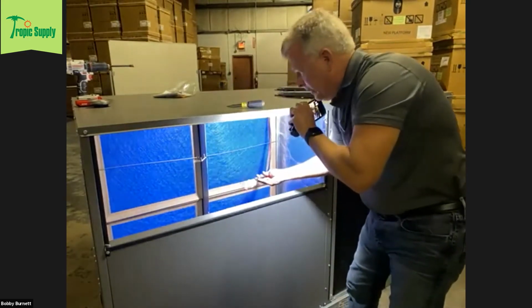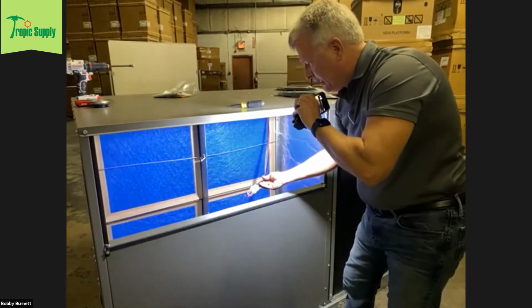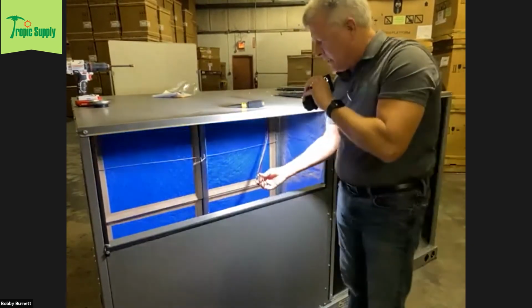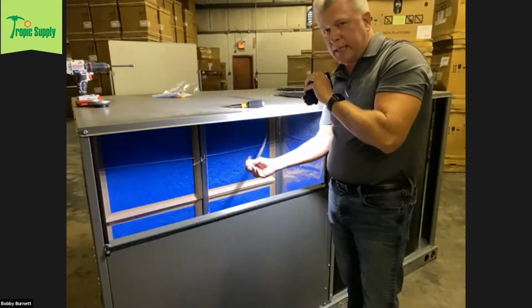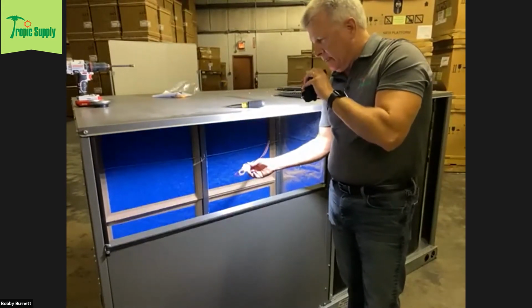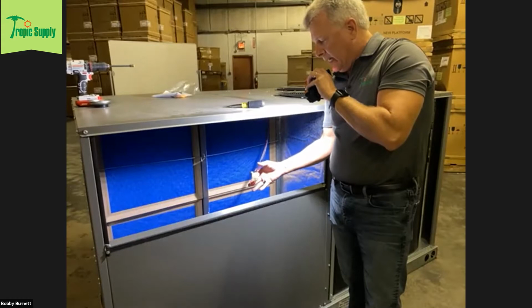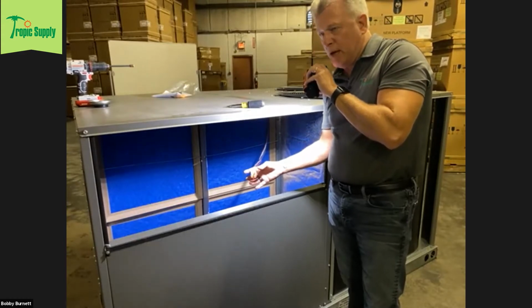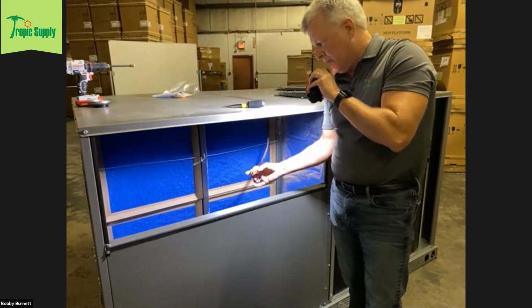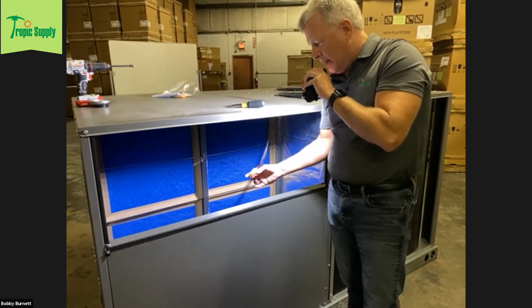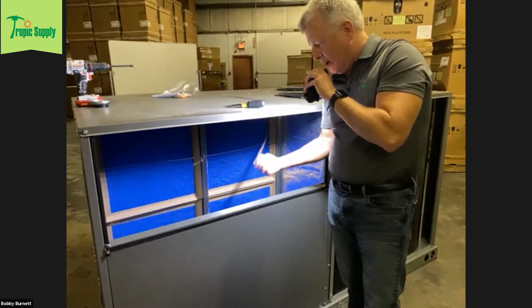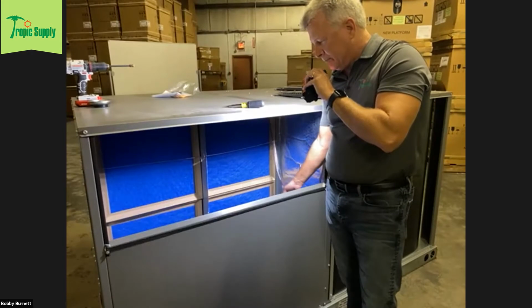This connection over here is if you're going to add an economizer to the system. One thing you want to be aware of, if you're going to unplug this and plug in to the economizer, you should keep this plug, because if you ever want to disable the economizer and run the unit without the economizer, you'll need to put that plug back on in order for the system to operate.